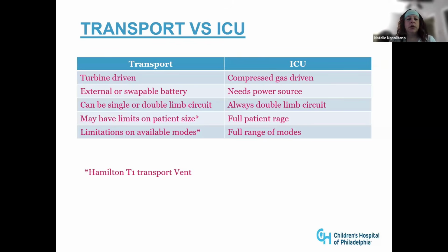Transport ventilators can usually have a single or a double limb circuit. Oftentimes, if you're going into a smaller neonatal pediatric mode, you have to use a double limb, and different expiratory valves and things can get a little complicated there. But the ICU ventilators are usually always a double limb circuit. You have a limit on patient size with your transport ventilators. Generally, there's a limit on low tidal volume or high pressure in a volume mode. So then you have to go to using a pressure mode, which oftentimes, we have to do even though we want to be volume ventilating.